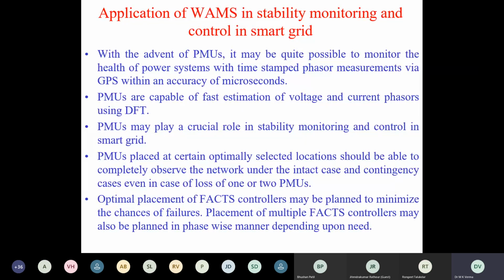So with these PMU measurements, you can obtain the power flow through the network, voltage at different buses, and the current flow through different lines. So you can check different constraints. You can monitor health of the system. You can monitor stability of the system with these real-time measurements. PMUs are capable of fast estimation of voltage and current phasors using discrete Fourier transform or fast Fourier transform. PMUs may play a crucial role in stability monitoring and control in smart grid architecture, where you need real-time control, and that can be done through PMUs.